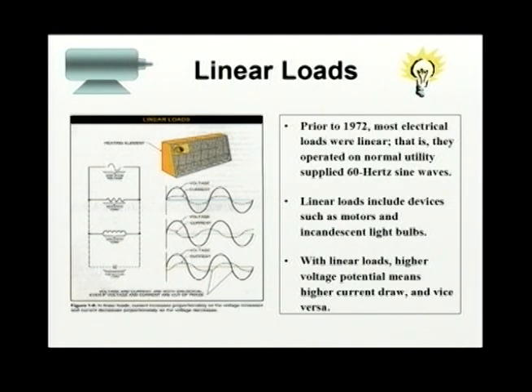Linear loads have a uniform voltage, frequency, and current draw. They produce no distortion of the waveform except when a switch is turned on or off. Light bulbs, electric heaters, and motors with a constant charge are examples of linear loads. Prior to 1972, most electrical loads were linear. That is, they operated on normal, utility-supplied 60 hertz sine waves, alternating current.